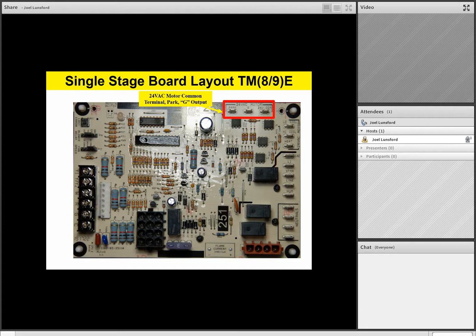Now remember, team, an ECM type of motor, which these are high efficiency motors on here. That E at the end of the model number, that TM8 or TM9E, means high efficiency motor. So these high efficiency motors have line voltage power to them all the time. And then we're going to command that motor with 24 volt inputs. So these 24 volt motor connections you see up here are part of that 24 volt control scheme.